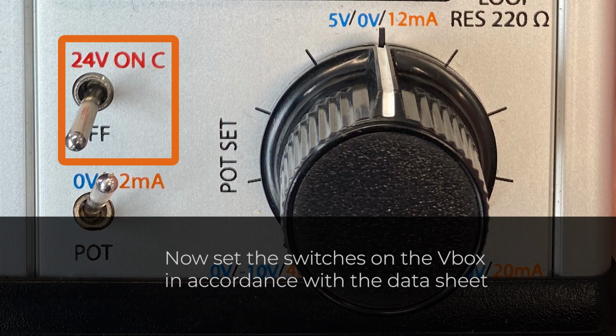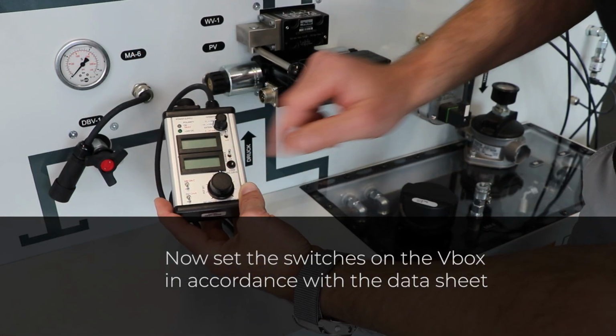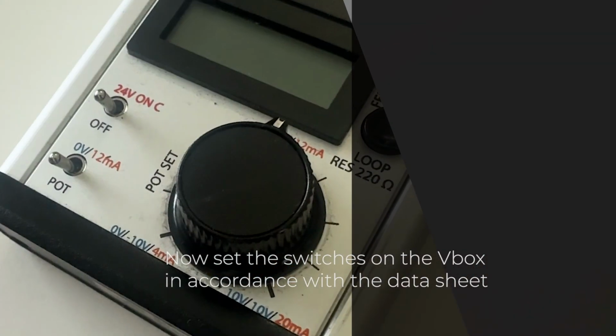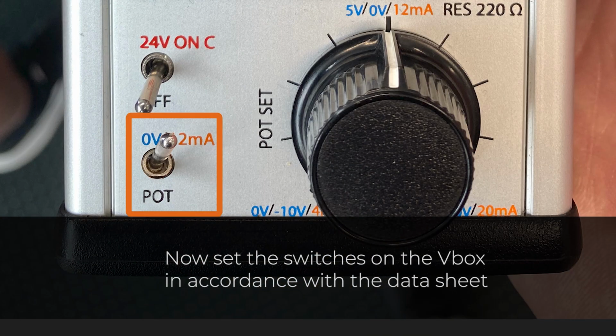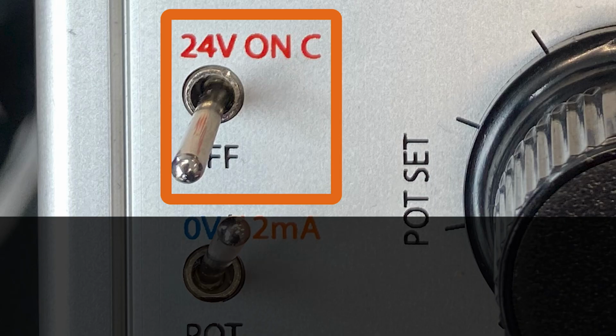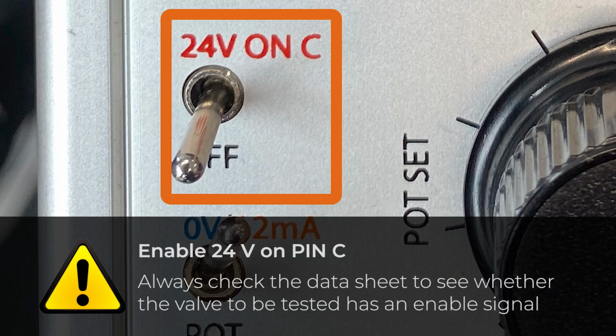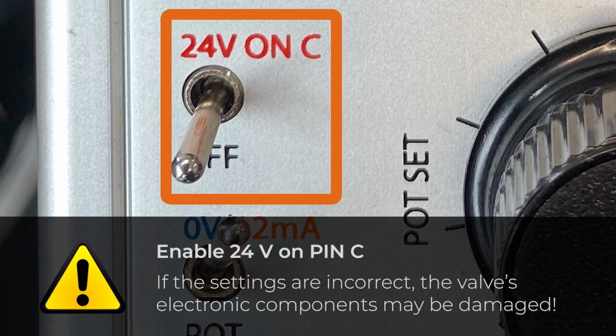We set the potentiometer to the center position, that is 0 volts or 12 milliamps. We also set the potentiometer selector switch to 0 volts or 12 milliamps. The enable function remains deactivated. Attention! The 24 volts to pin C enable switch must always remain deactivated for valves without an enable signal. Particular caution is required here. If the enable function is activated on a valve without an enable signal, the valve electronics may be damaged. In our example, the switch remains set to off because this valve does not have an external enable signal.